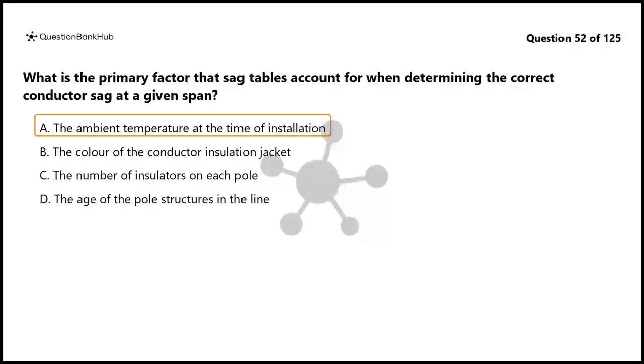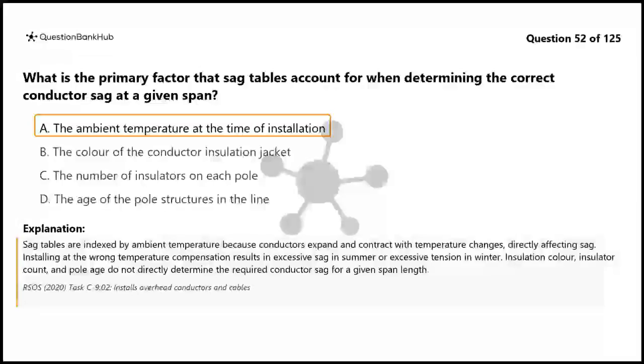The correct answer is A. Sag tables are indexed by ambient temperature because conductors expand and contract with temperature changes, directly affecting sag. Installing at the wrong temperature compensation results in excessive sag in summer or excessive tension in winter. Insulation color, insulator count, and pole age do not directly determine the required conductor sag for a given span length.